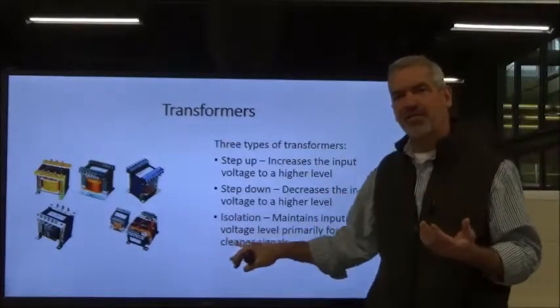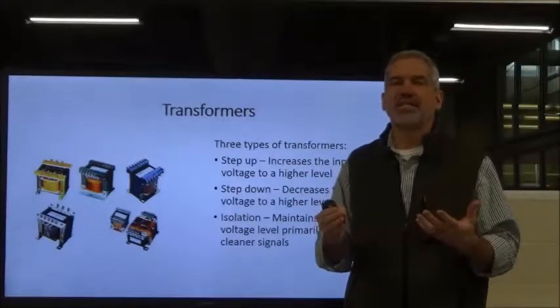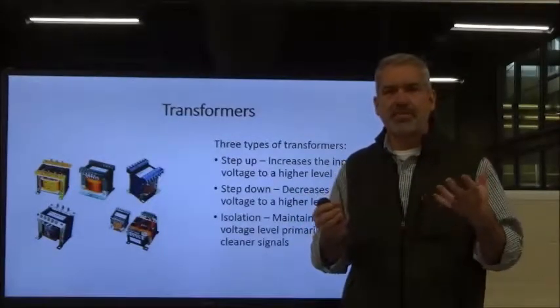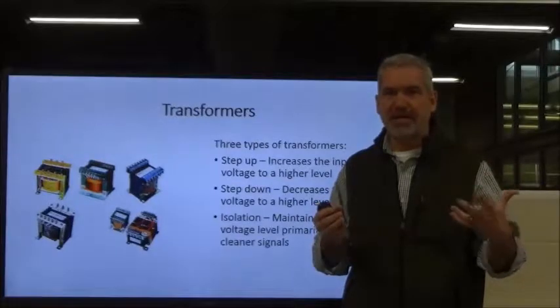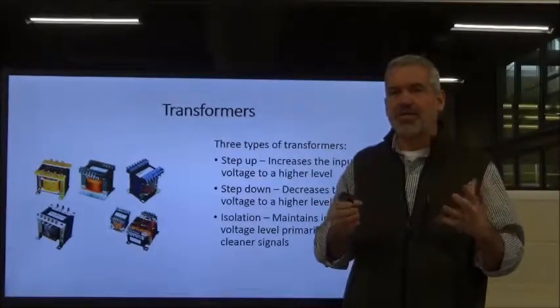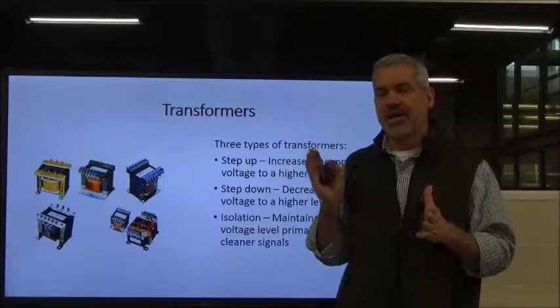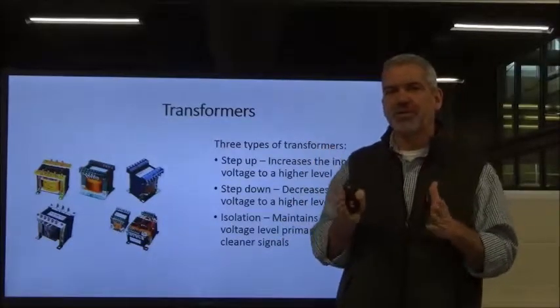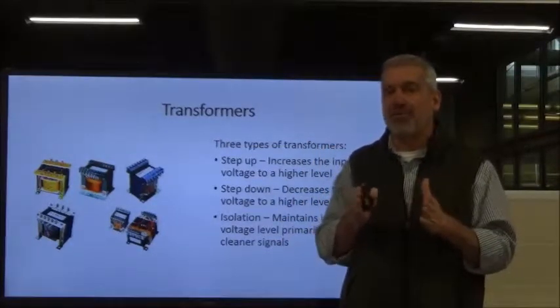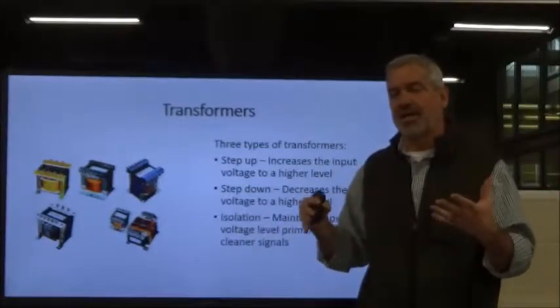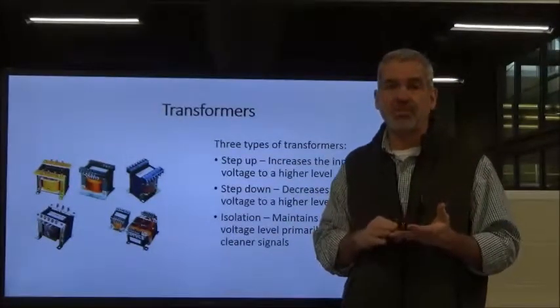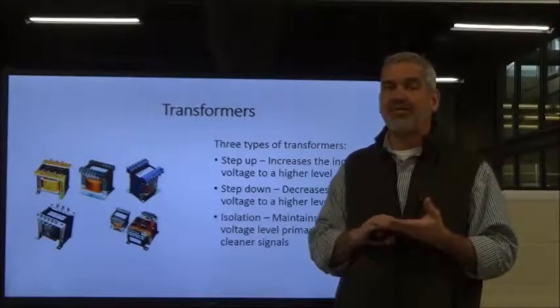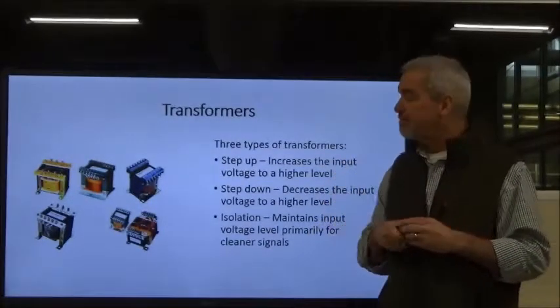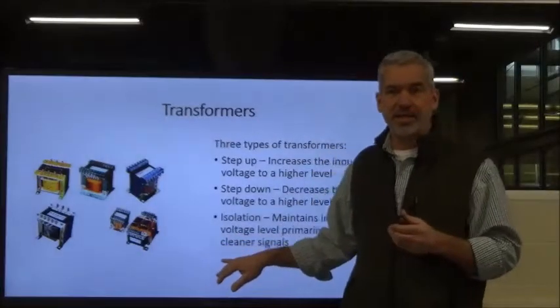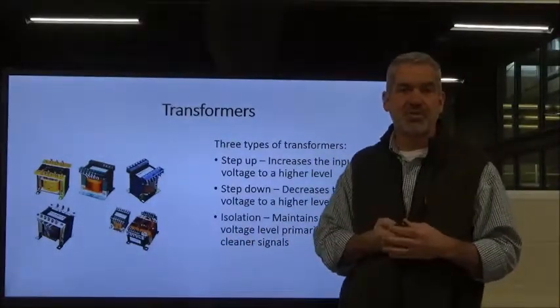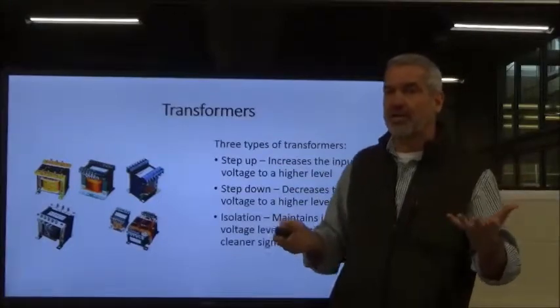I'll just speak briefly on this one. The reason we have isolation transformers is because sometimes power coming in is dirty, it's got spikes and some fluctuations. An isolation transformer will buffer out those spikes and clean the power up. So a lot of times, particularly when there are PLCs, robotics, process control, things that are very susceptible to spikes, we want clean power going into those systems. So we always use an isolation transformer that doesn't raise or lower the incoming voltage.